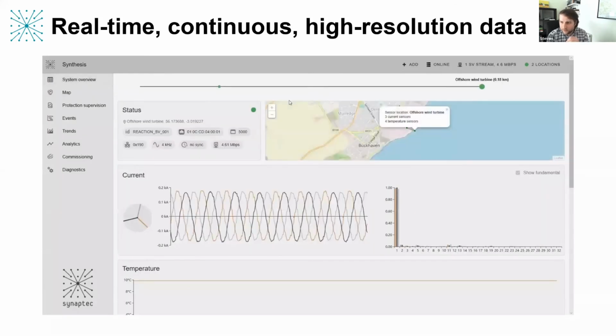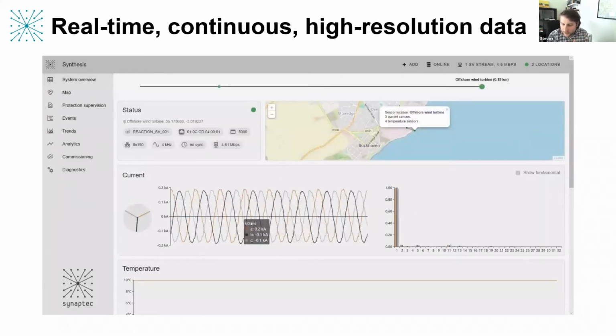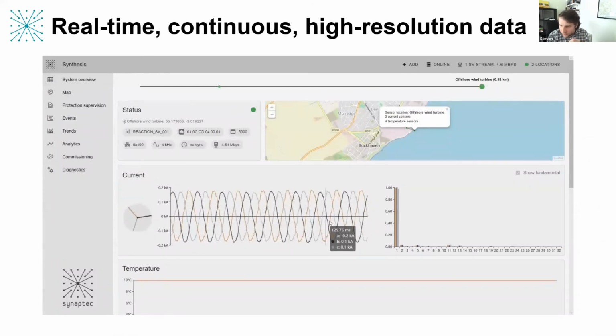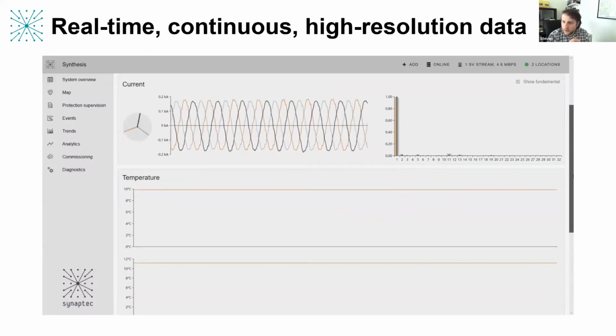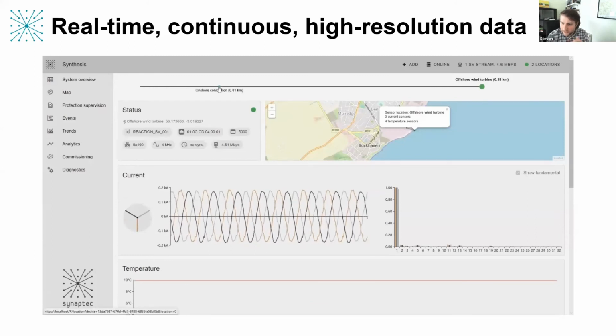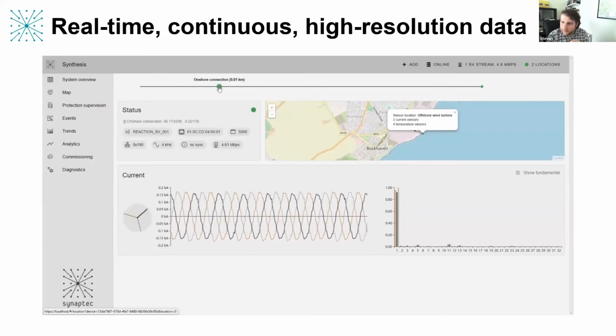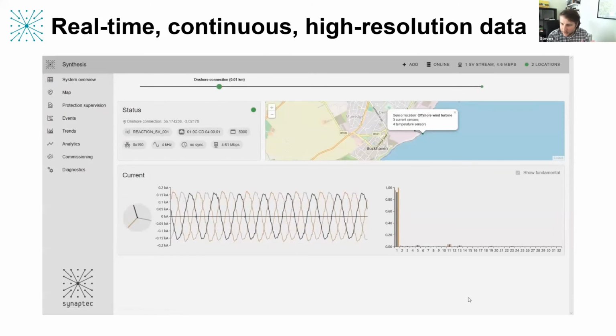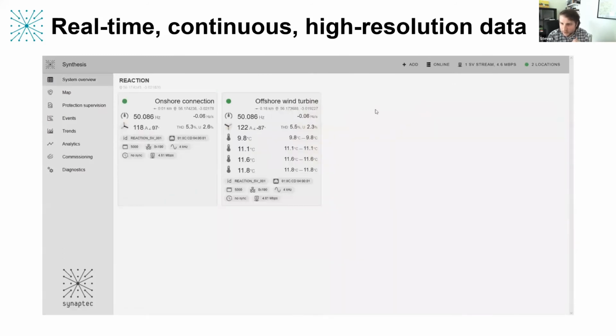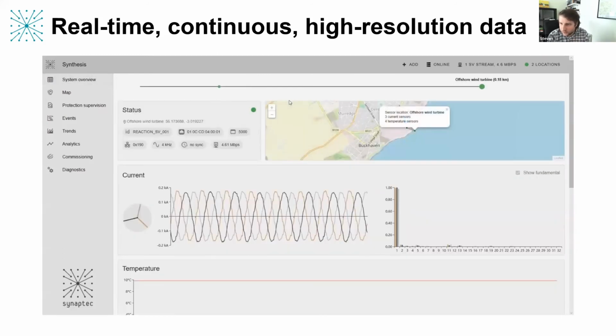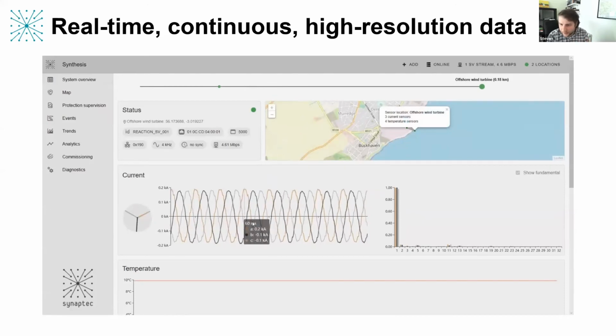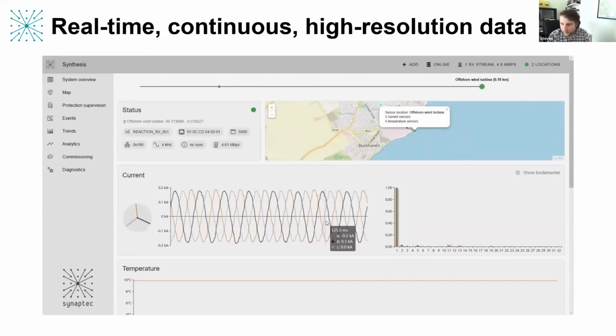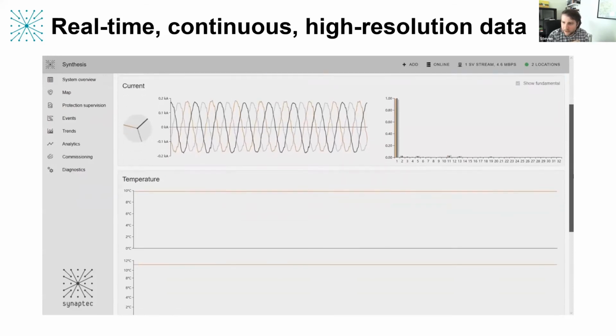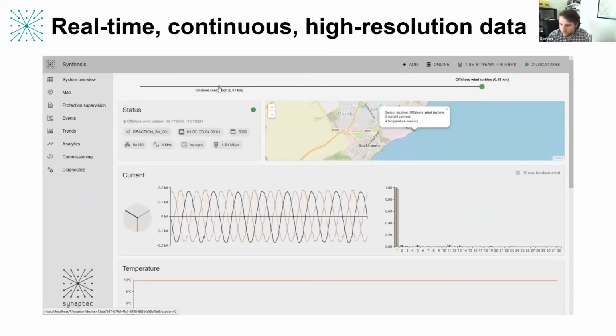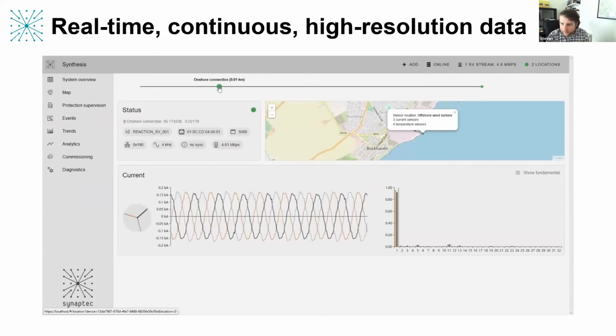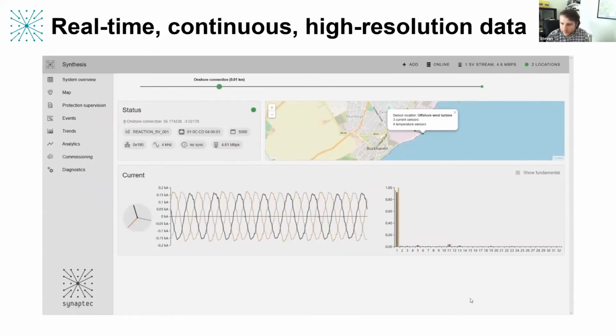So for that first installation, this is pre-recorded, but this is the actual streaming data that we get. This is the telemetry that we get from that system. Again, this is a relatively simple installation with a low number of sensors, but here you can see a summary of all the sensor data that we get. You can see the detailed waveform information that we're collecting, and on the right of the waveform, you can see the harmonic spectrum for the current measurements taken there.